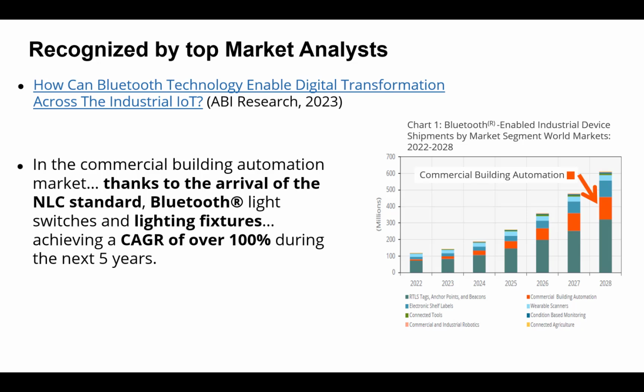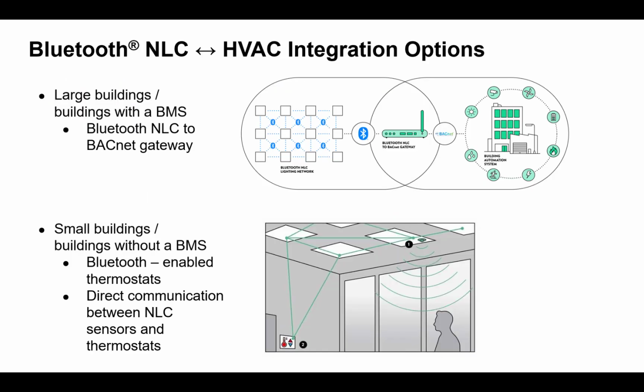They just work together. So now, where's the HVAC part? The HVAC part with Bluetooth NLC can be done in two ways: for large buildings and for small buildings. In large buildings, the assumption is there's a building management system, and in the BMS world, BACnet is typically the reigning protocol. So it's easy to imagine a gateway product which sits between the Bluetooth Mesh lighting network and the BACnet subsystem, and that BACnet gateway simply provides data communication back and forth.